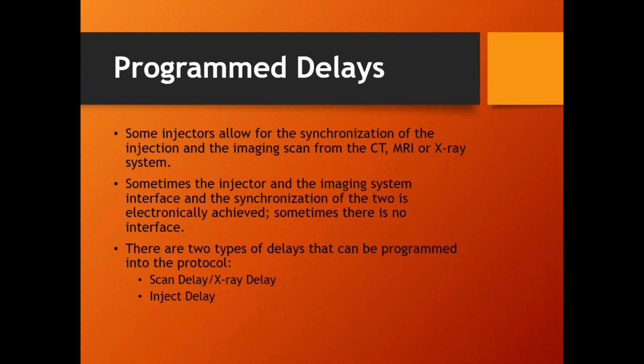I'm going to program in an inject delay, a 5-second inject delay, meaning once the X-ray system starts shooting, let's say it's a 5-second delay, 5 seconds later, the injector starts injecting the fluid, all right? Simple enough. CT, MRI, angio, they all call it that, injection delay. Now the opposite of that goes by 2 different names, scan delay and X-ray delay.